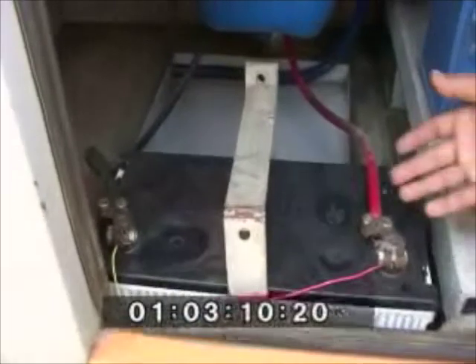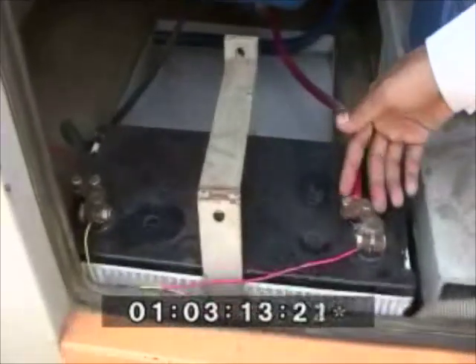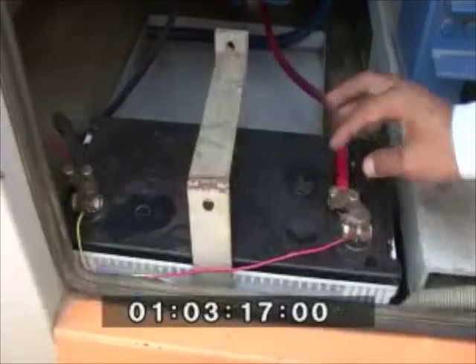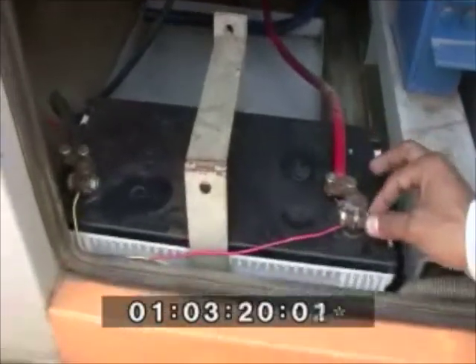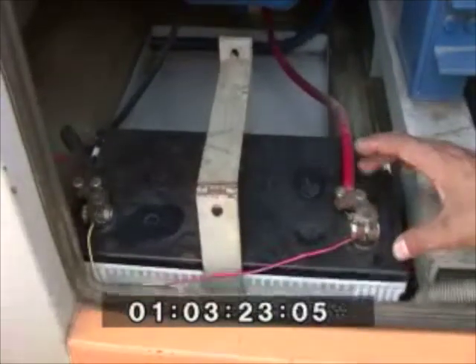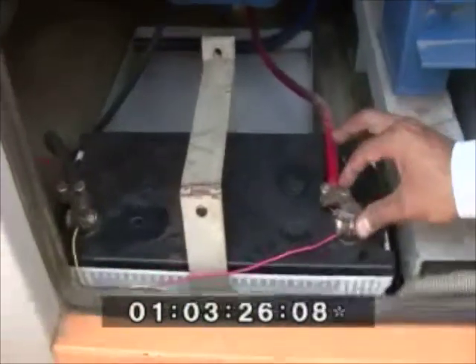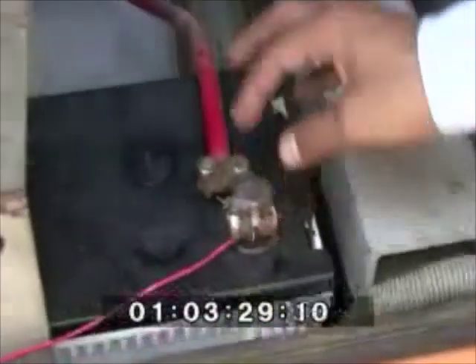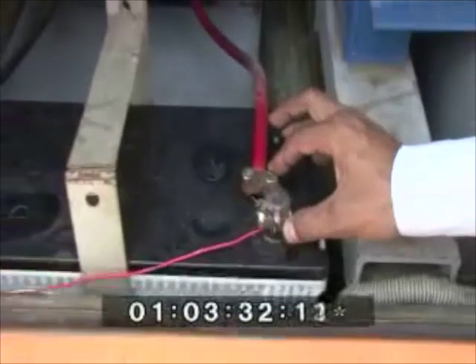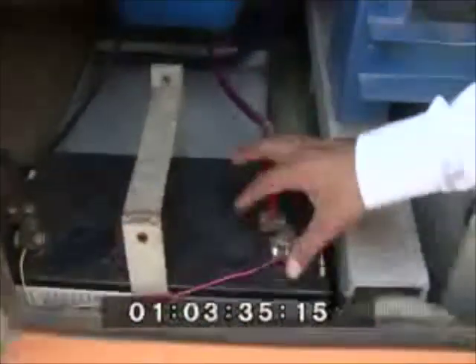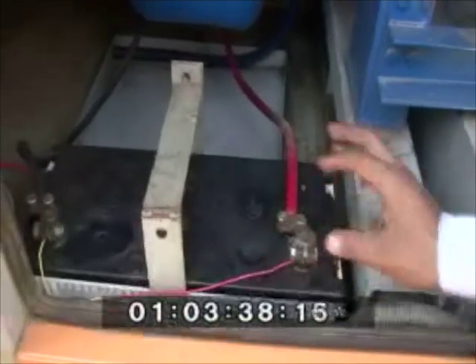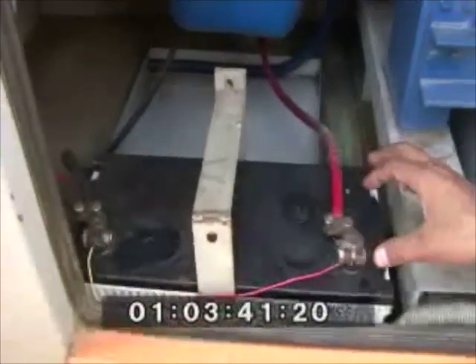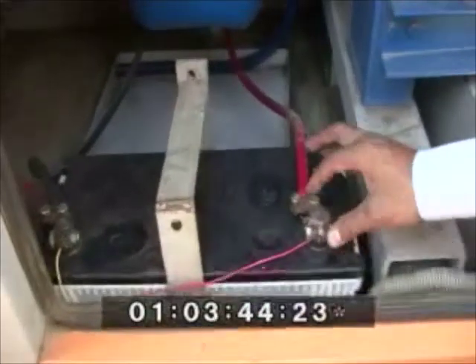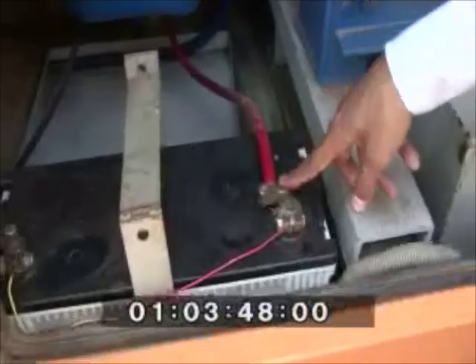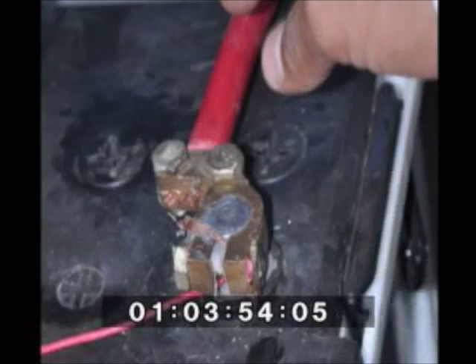We should also check for carbon depositions on the terminals. We need to check if the jelly has been applied on these terminals to avoid the carbon deposition. To maintain proper connectivity of the cable to the connector, the two nuts on the connector are to be tightened. To tighten the connectors, the nuts on the terminal of the battery are to be tightened.